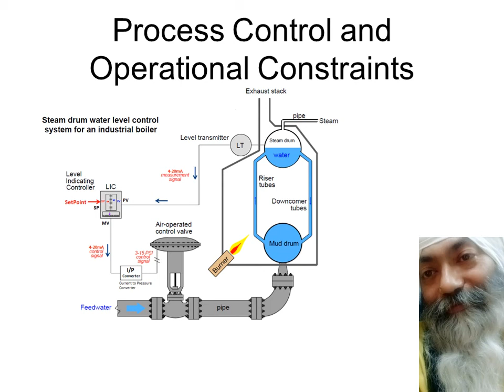So let's revise it: a boiler level overflow will contaminate the steam with water. It's containing some undesirable dissolved solids, and at the same time if the water level goes down, it will damage the tubes, and we have to control this entire process through LIC. As you can see, you have this thing called LIC, the level indicating controller. This is the intelligent controller which is going to decide, which controls this valve and maintains the level at the desired point, which is something around 50% or 60% of the steam drum as it may be designed for.